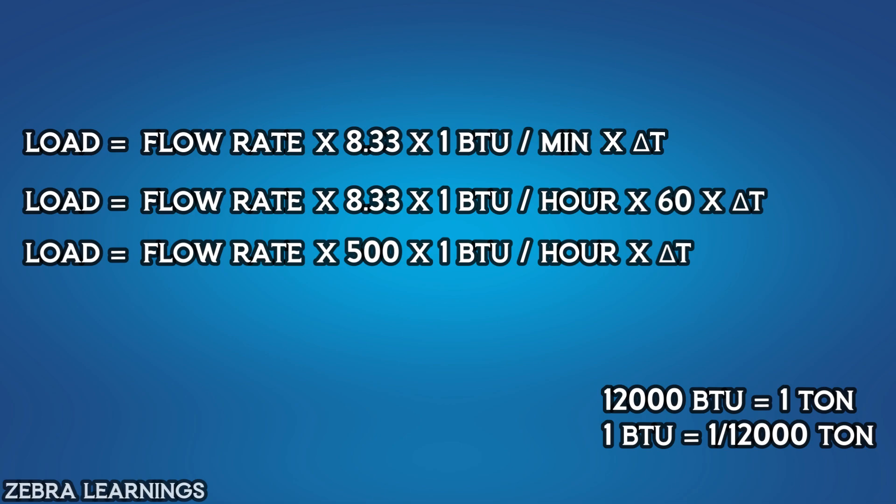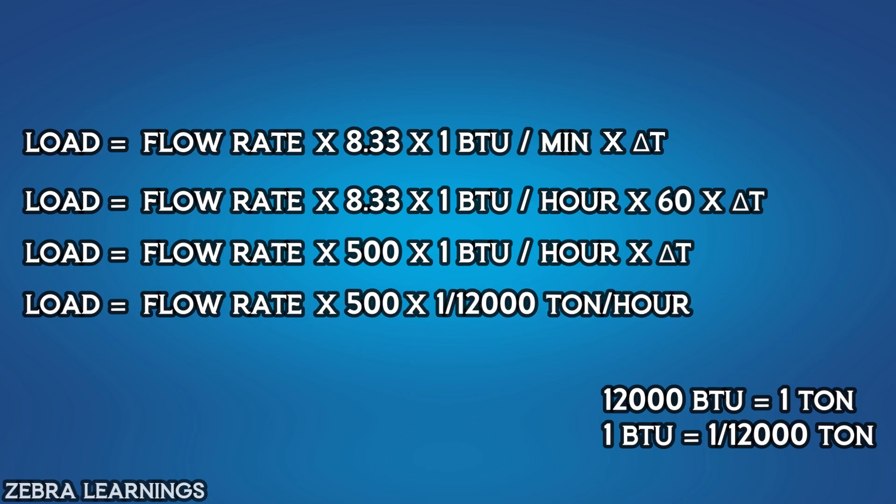Let's use this value in the formula. Load equals flow rate multiply 500 multiply 1 by 12,000 ton per hour in place of 1 BTU, multiply delta T.